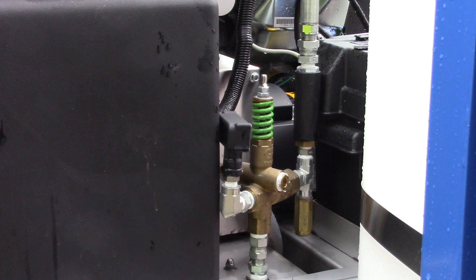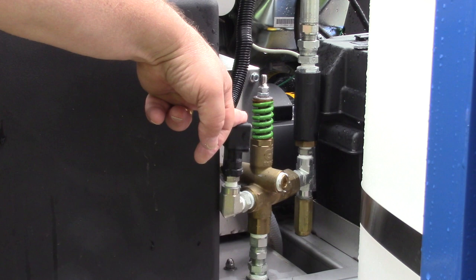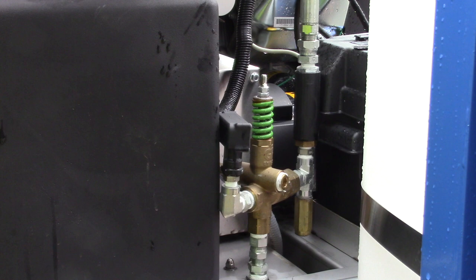The other devices — that's a pressure switch we talked about, no pressure, no heat. Pressure is right here. We have a spare one of these in the bin for you. This is a flow switch — it monitors when flow is running through the high pressure hose. High pressure cold water is coming off the pump, going into the valve, then cold water high pressure goes into the heating coil. The heating coil is actually under pressure, running at the rated pressure, and every time the gun's off it's rated for the bypass pressure too. That's the typical way almost every hot water unit out there works.